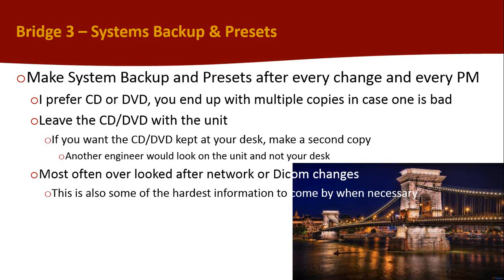The last thing I'd like to say is I know a lot of engineers that do this, and they make backups, and they're really good about it, but they put them in their desk, usually under lock and key. Well, that's good, and that's actually great. The problem is, if I get called in, it's probably because they're on vacation or they're out sick, and then I don't know where that is and don't know where to find it and wouldn't expect it to be under lock and key. So what I would say is leave a copy with the unit. Take a second copy back to your desk. That way you know you have a copy that's secure, because we know they can walk away. But try and leave one with the machine, because that's where we, as a service representative coming in from outside the hospital, would expect it to be with the machine.